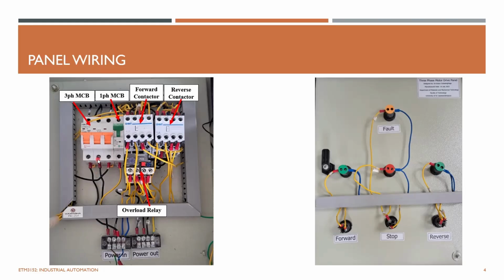When the main power comes, it directly goes to the three-phase main circuit breaker, where you can isolate or disconnect the power to the downstream devices. Another single-phase MCB is used to connect or disconnect the power to the control wiring. Sometimes you can use a single-phase MCB or sometimes a two-pole MCB if you want to isolate the neutral as well. But in this circuit, only the live terminal, one of the live wires from the three phase, is connected to the single-phase MCB, and the neutral is directly connected to the neutral.